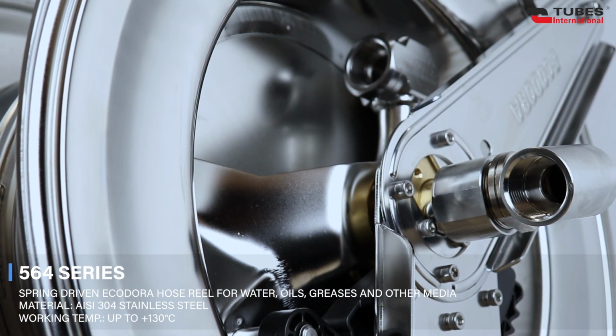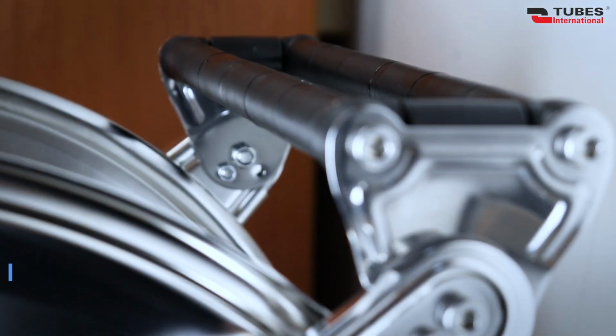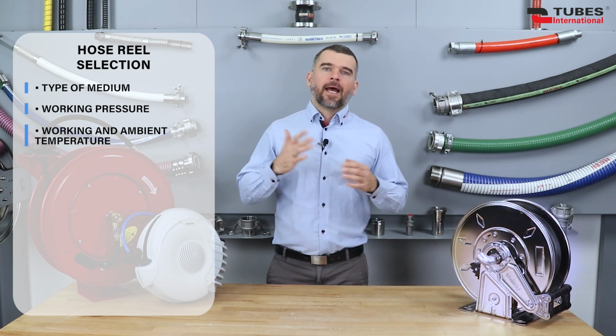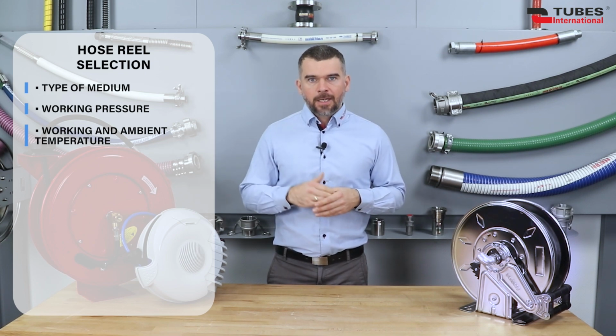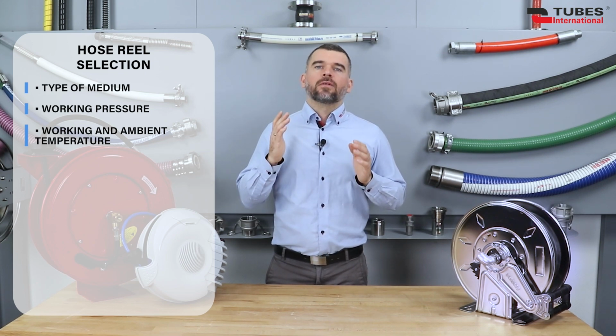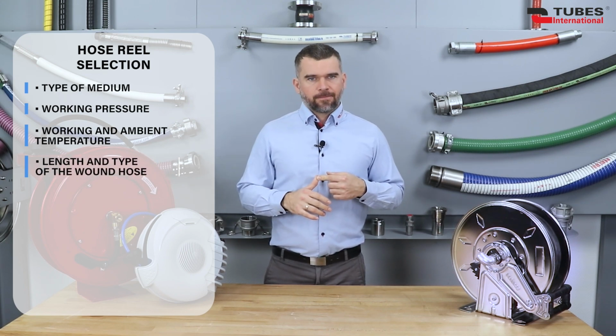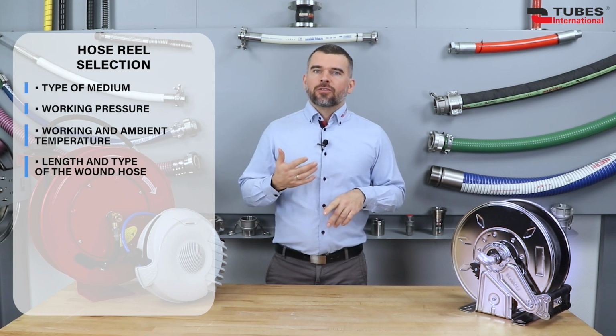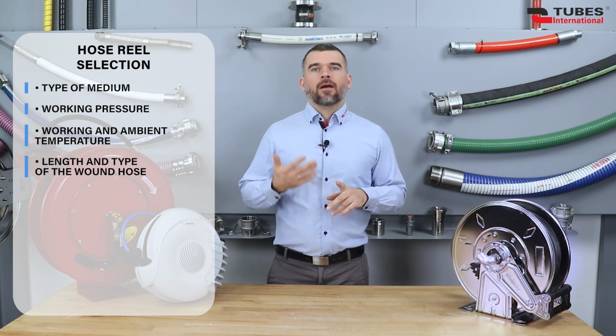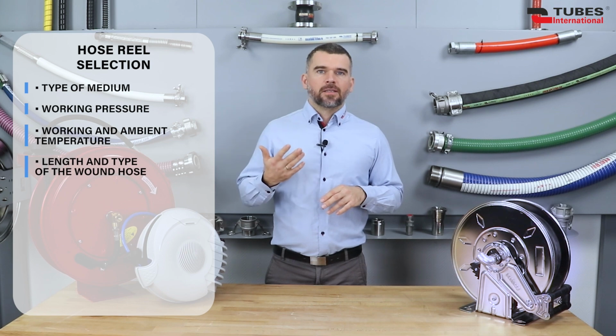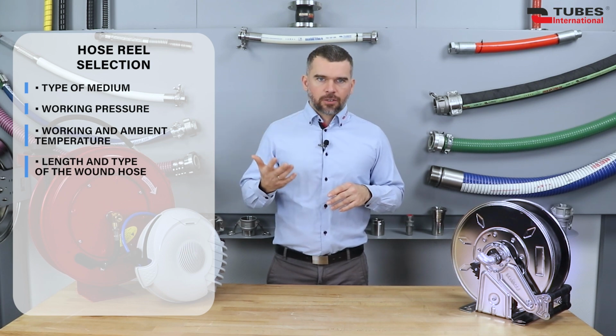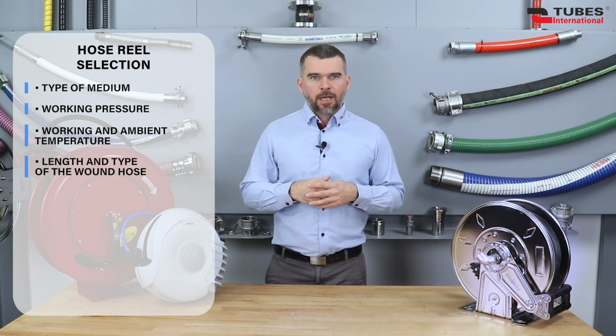Remember one important rule: if the maximum pressure of the reel in a set is 35 bar and the hose is rated for 20 bar, the maximum pressure of the entire system is always equal to the lower value, which is 20 bar. The same principle applies to temperature. Additionally, pay attention to hose length, hose type. Not every hose is suitable for winding on a reel. Hose with an external steel braid may be damaged due to friction and pressure between the coils.